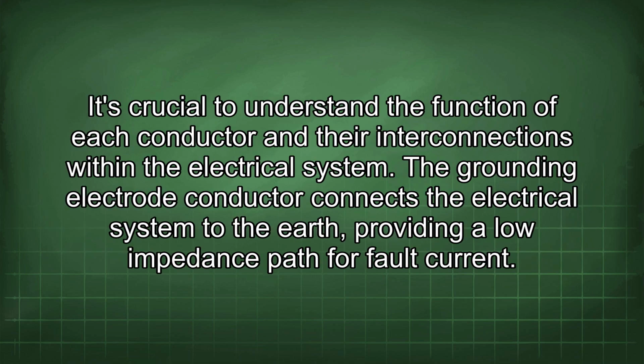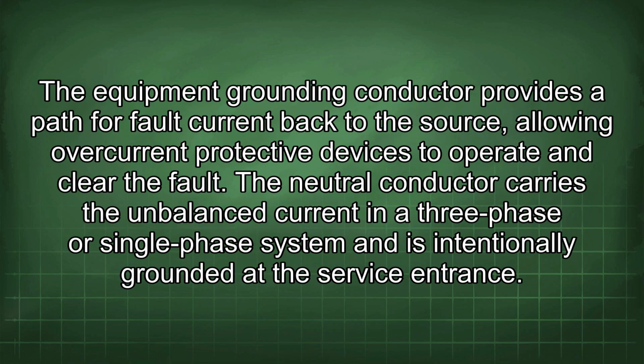It's crucial to understand the function of each conductor and their interconnections within the electrical system. The grounding electrode conductor connects the electrical system to the earth, providing a low impedance path for fault current. The equipment grounding conductor provides a path for fault current back to the source, allowing overcurrent protective devices to operate and clear the fault. The neutral conductor carries the unbalanced current in a 3-phase or single-phase system and is intentionally grounded at the service entrance.